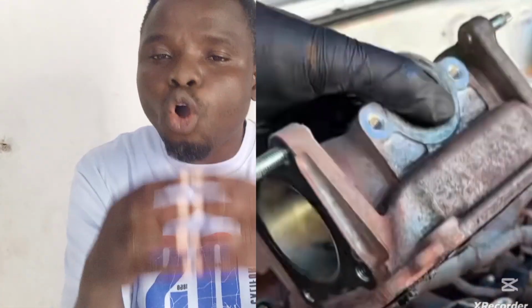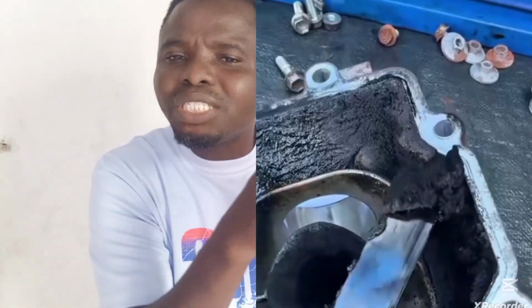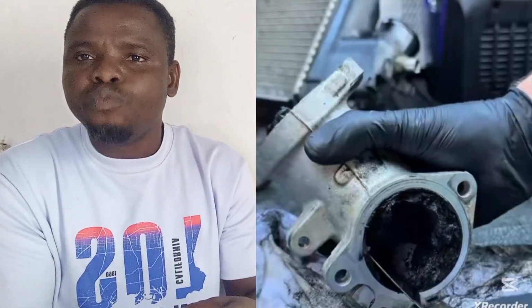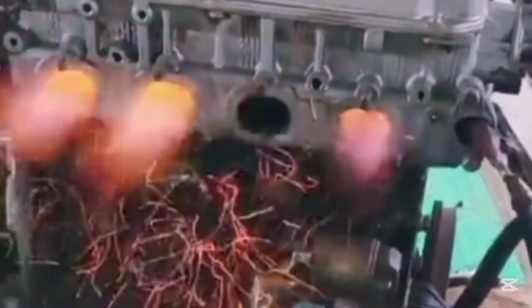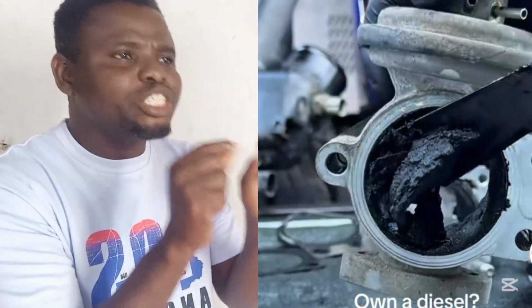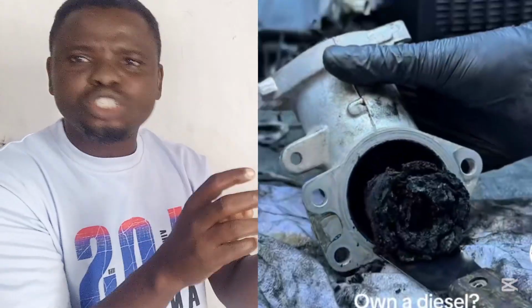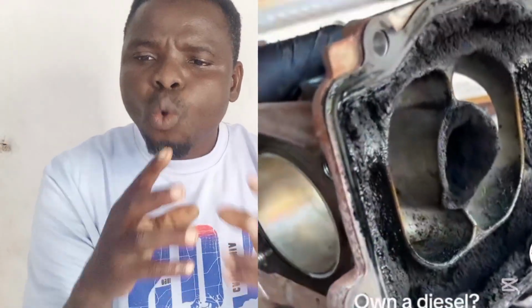Wet stacking is usually caused when a diesel engine runs for a very long time without enough load. That is why it's very common in generators. When you see a heavy duty generator, you most likely see wet stacking, because running the generator under insufficient load results into this. Diesel engines are built to run hot and hard so there won't be incomplete combustion. When you see oil coming from your exhaust, dripping down, that tells you that you are having what's referred to as wet stacking.